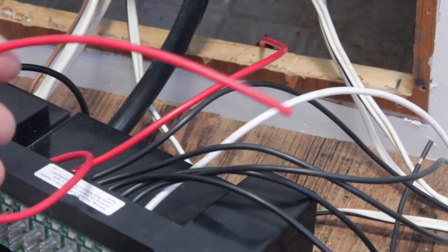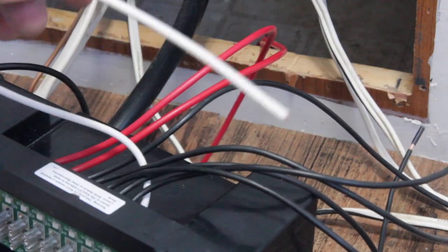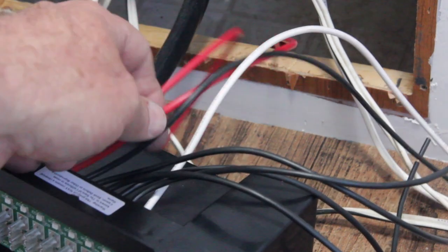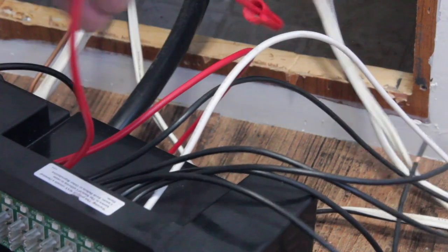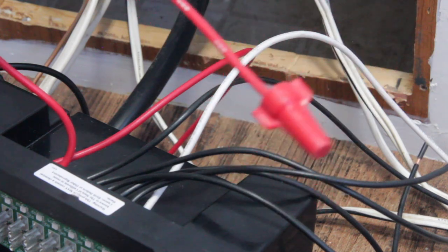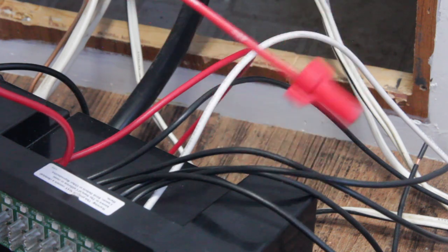On the DC side we have the red wire which is going to go to the positive terminal of our battery bank. The white wire is going to go to the negative side of our battery bank. I'm going to wire those in later when I'm ready to wire in the battery. The second red wire I have terminated because I'm not going to use it — I don't have any 30 amp AC circuit requirements at the present time, so I'm just going to terminate that with a wire nut.